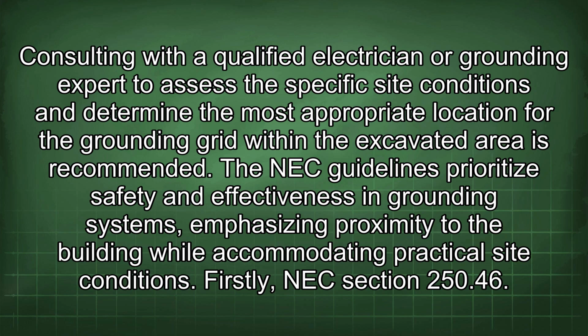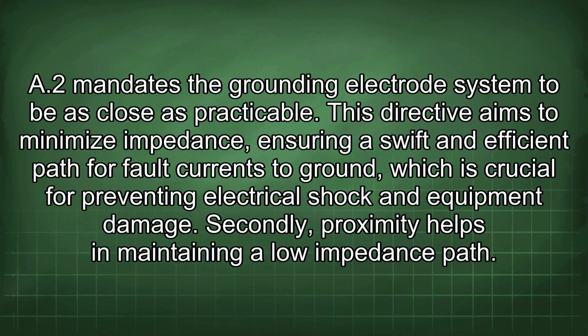The NEC guidelines prioritize safety and effectiveness in grounding systems, emphasizing proximity to the building while accommodating practical site conditions. Firstly, NEC section 250.46. A2 mandates the grounding electrode system to be as close as practicable. This directive aims to minimize impedance, ensuring a swift and efficient path for fault currents to ground, which is crucial for preventing electrical shock and equipment damage.